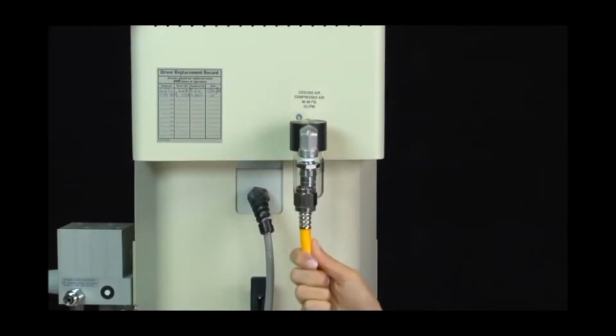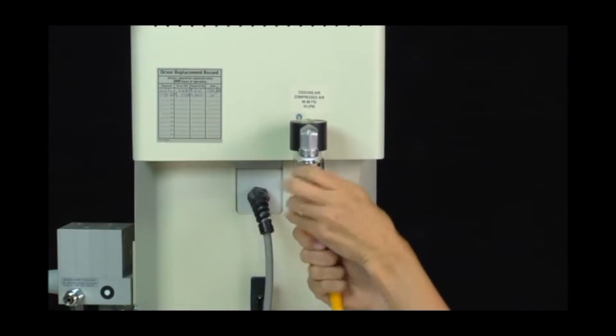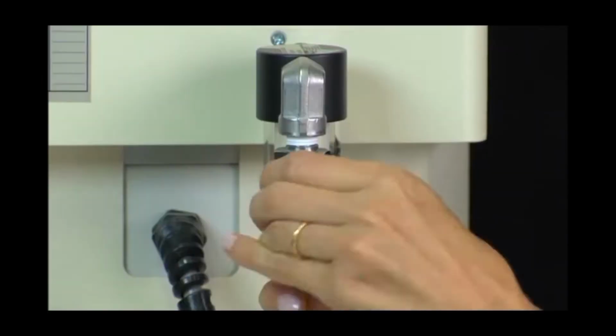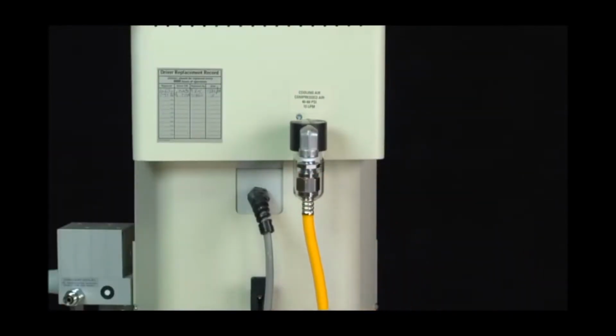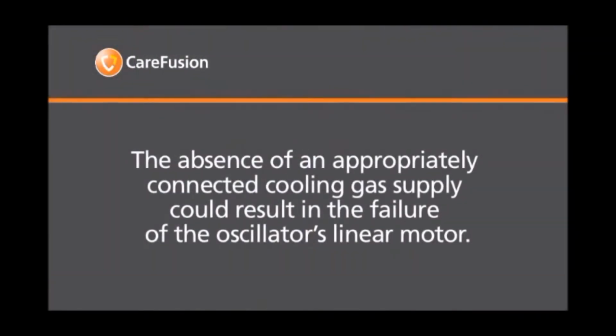A second DISS connection is labeled cooling air. This connection accepts a 50 psi compressed air supply, which cools the oscillator. It's important to note that the absence of an appropriately connected cooling gas supply could result in the failure of the oscillator's linear motor.